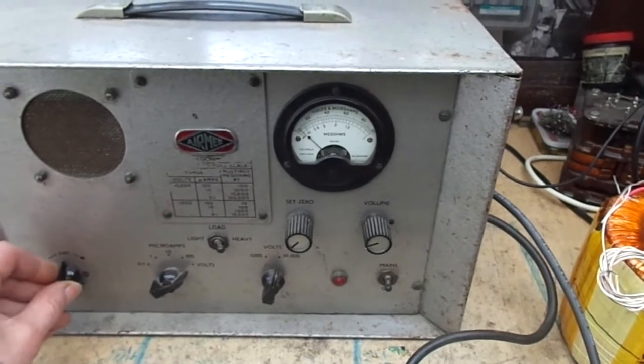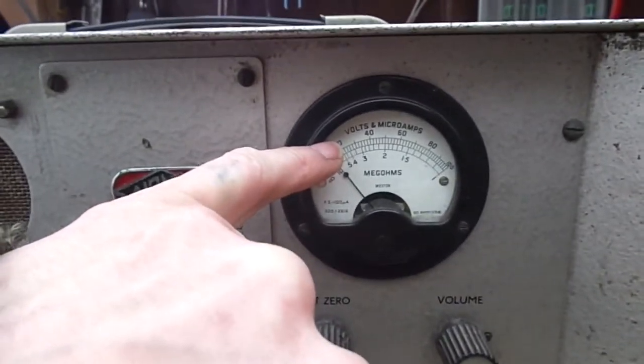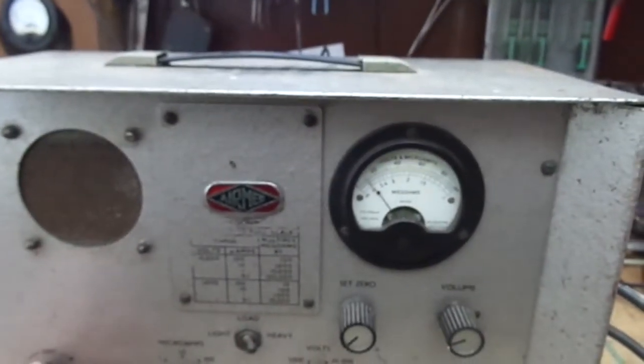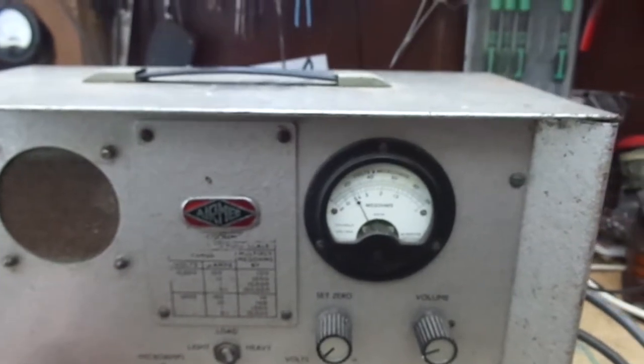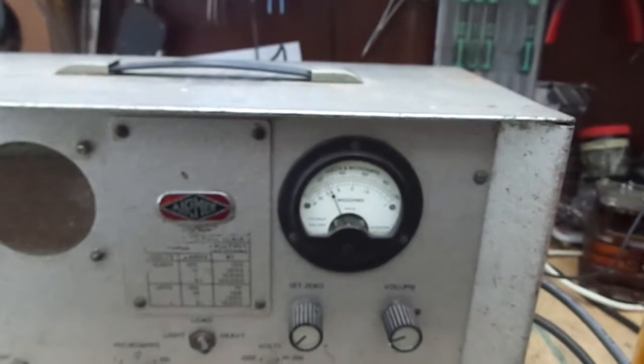Well there's a thousand volts there, so this is two thousand, four thousand, six, eight, ten. So at two thousand volts there's no insulation breakdown, just the odd click.